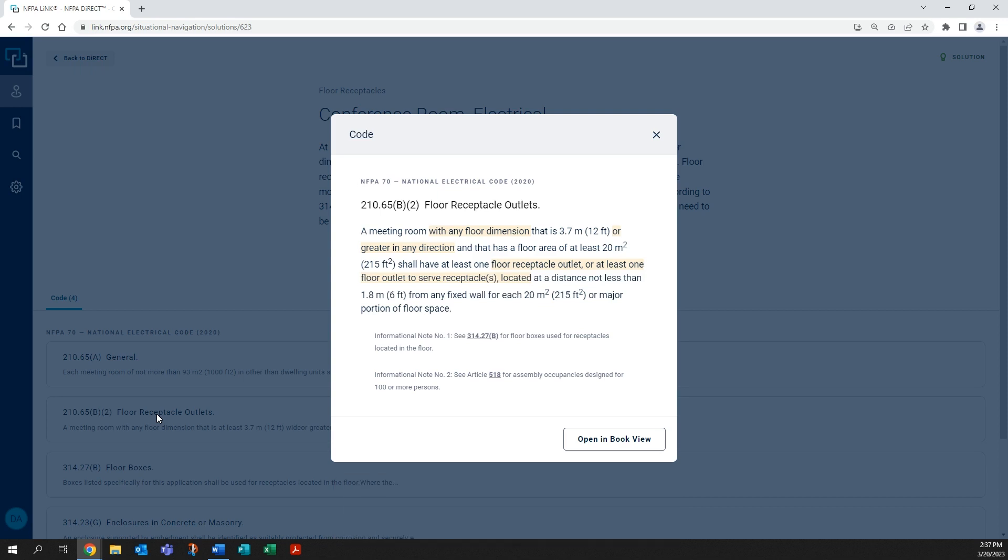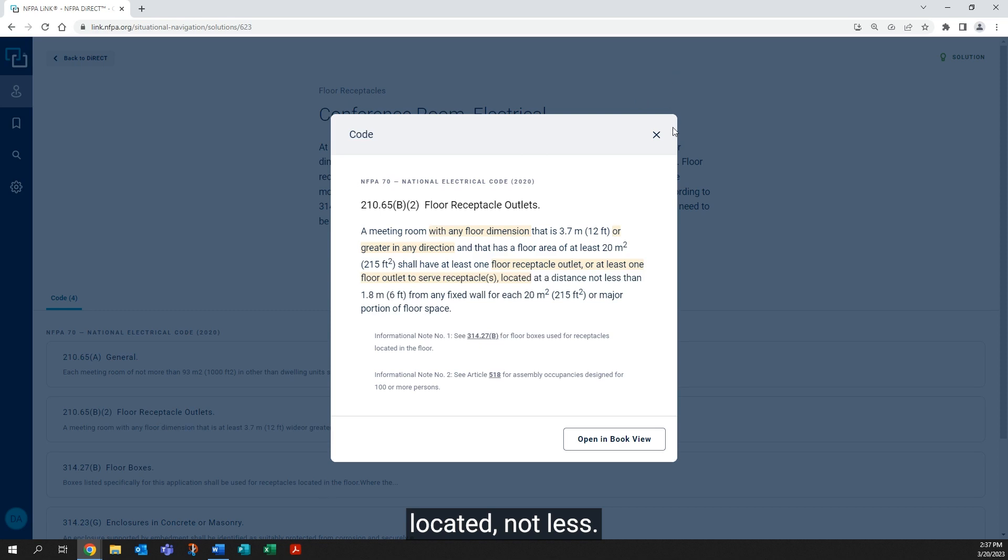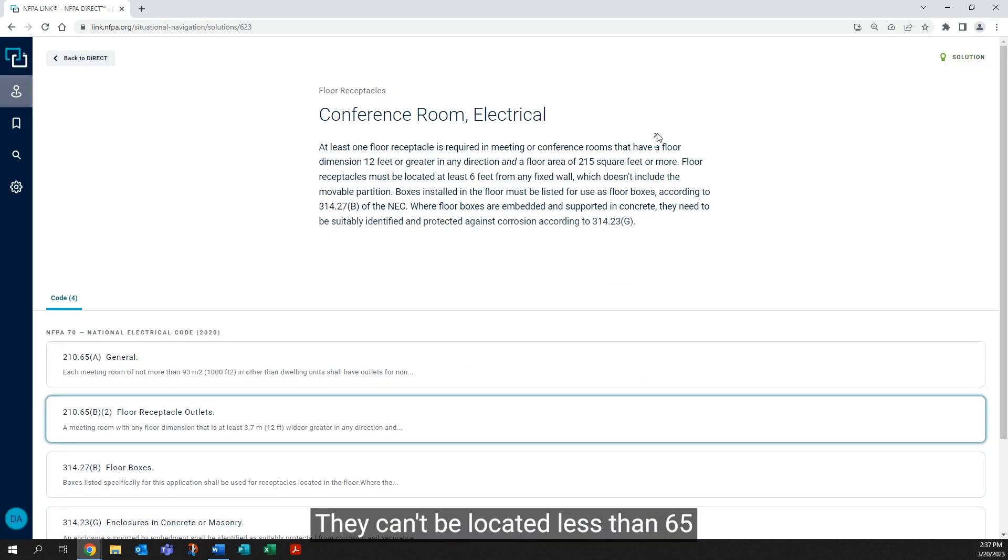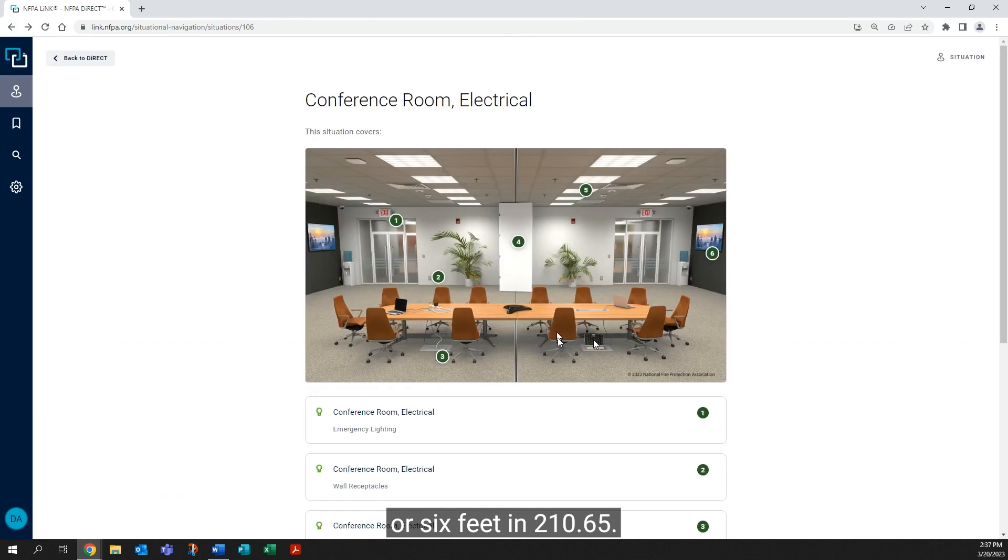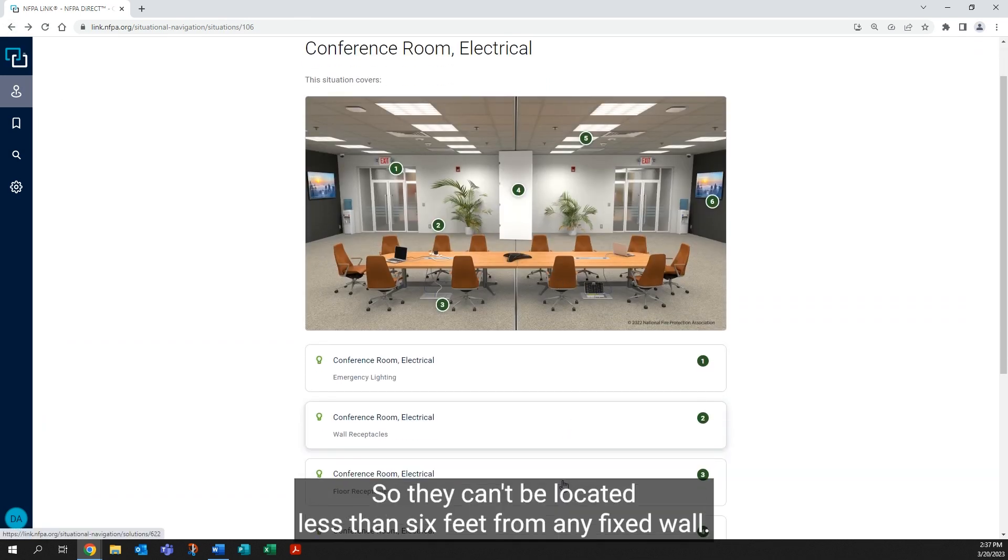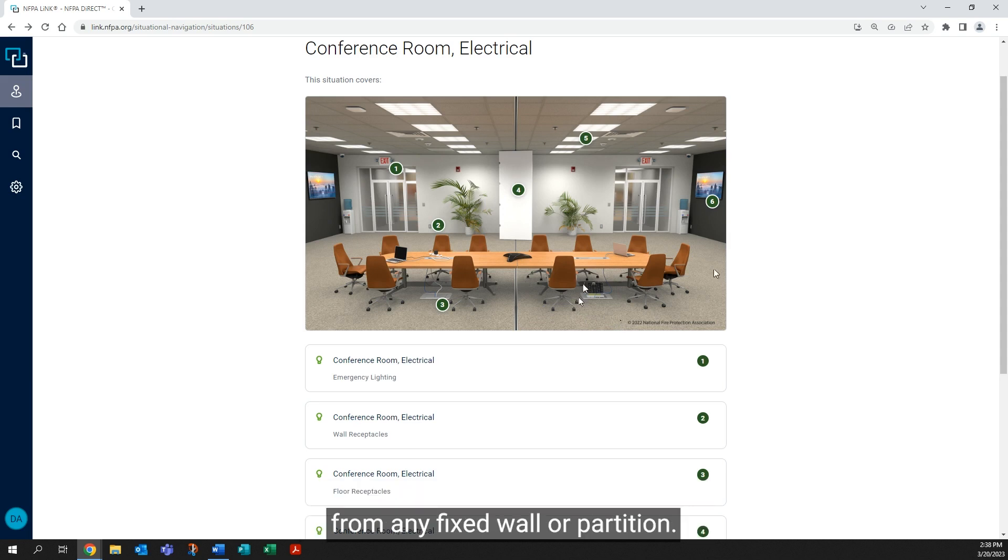So these receptacles would need to be located not less—they can't be located less than six feet, or six feet in 210.65. So they can't be located less than six feet from any fixed wall. And you'll notice in our artwork here, they are more than six feet from any fixed wall or partition.